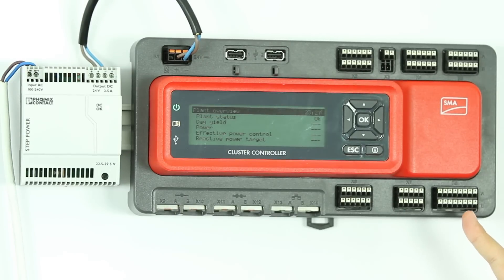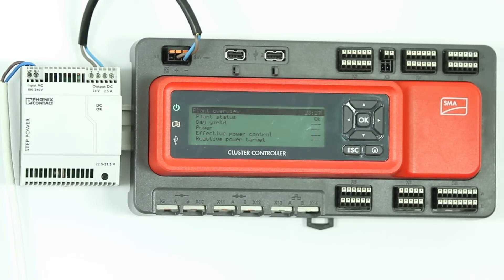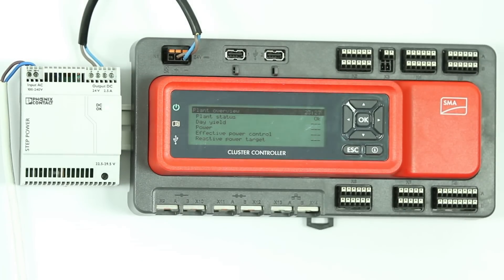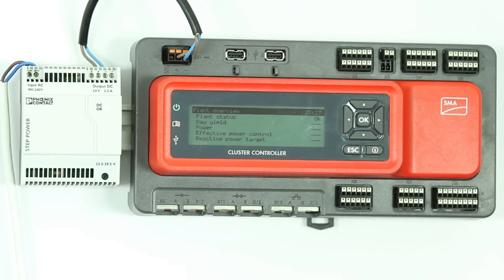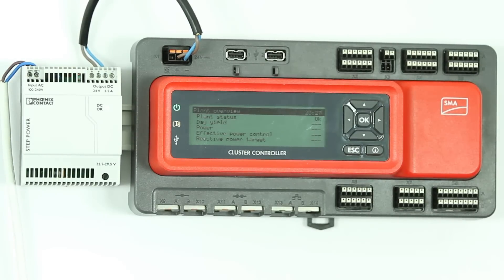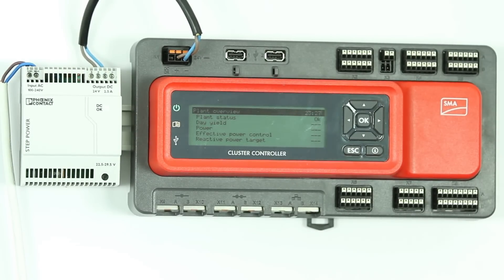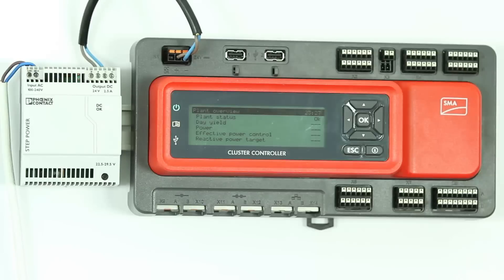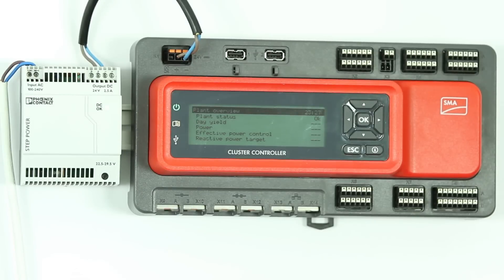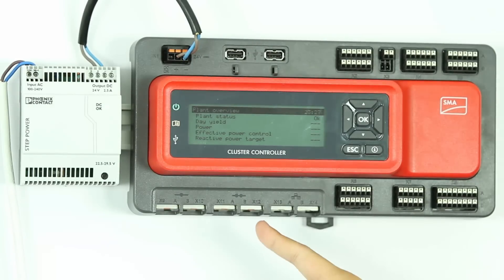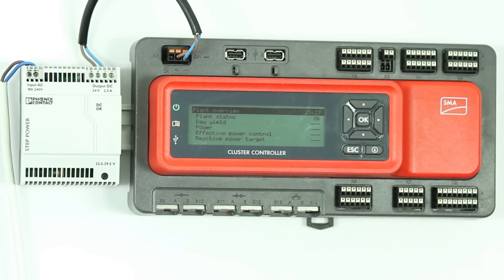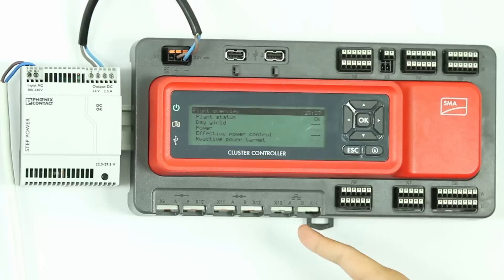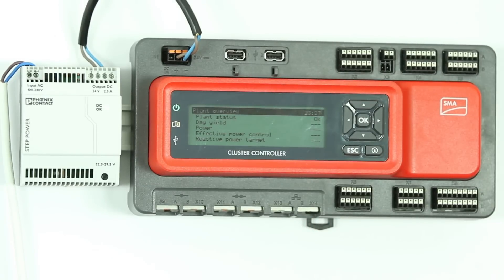X8 allows for four analog inputs, three current inputs for the radiation sensor, active and reactive power limitations and one voltage input for connection of a sensor. X9 and 10 is for the Speedwire network of the inverters. X11 and 12 is reserved for future applications. X13 and 14 are for the local area network connections.